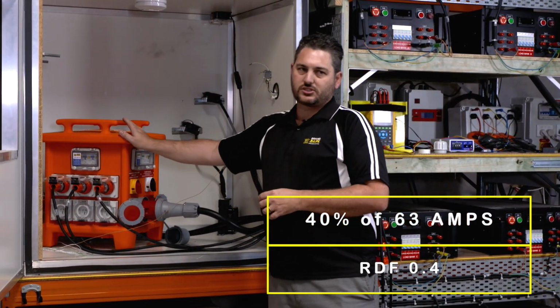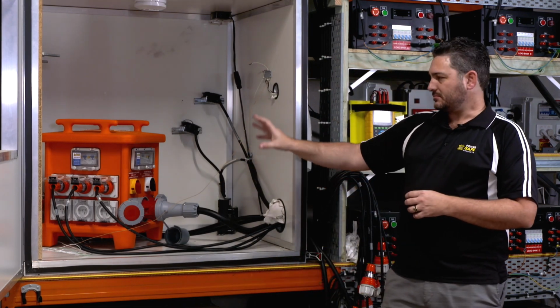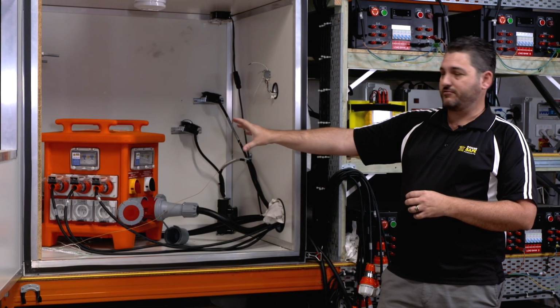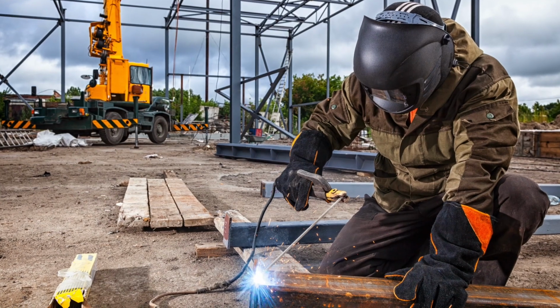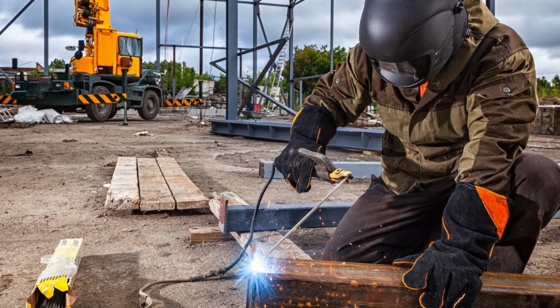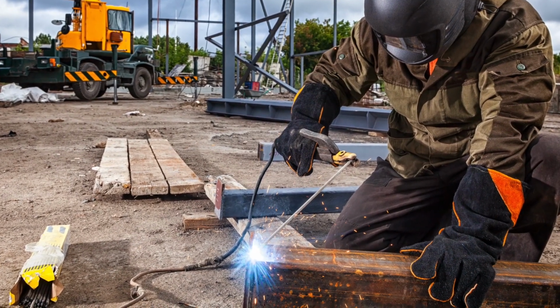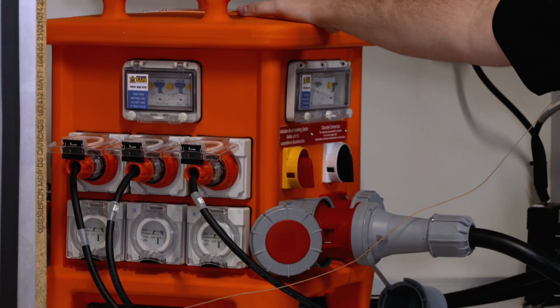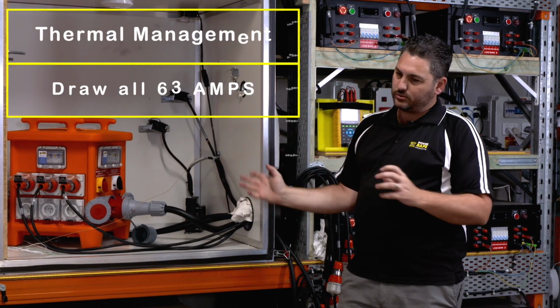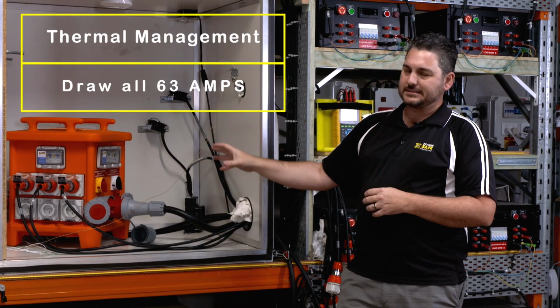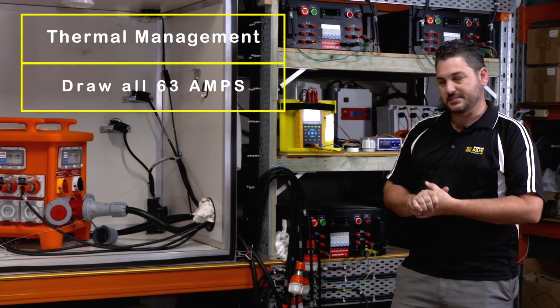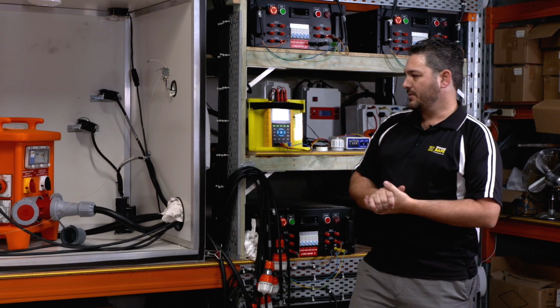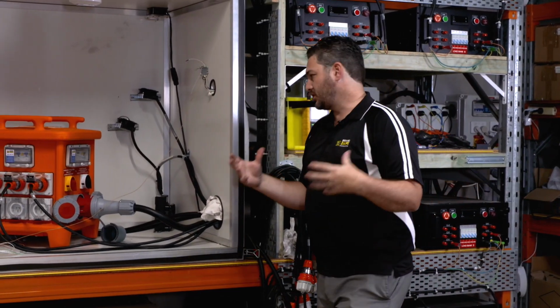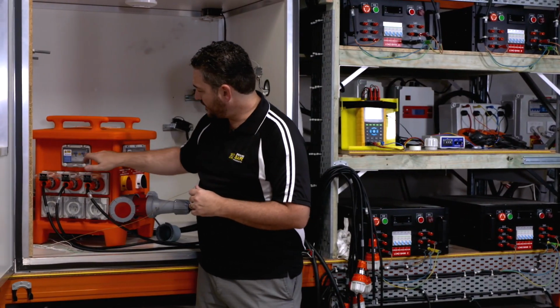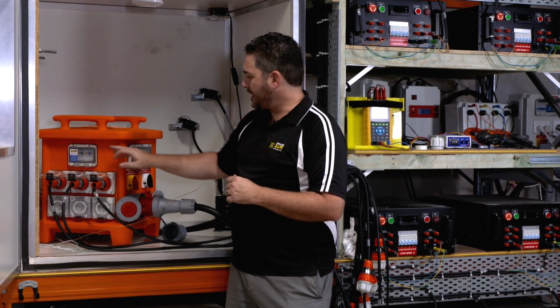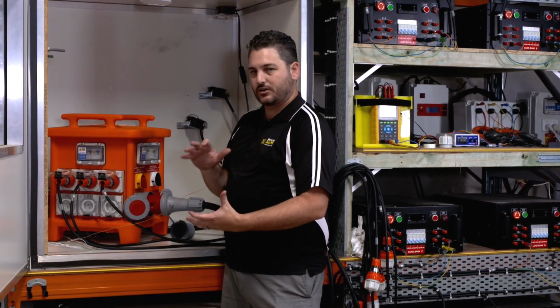So if that's going to a site with sporadic use, that board as it sits would work fine. If it's going to a mine site where they're doing welding, using heavy equipment, you will then use our thermal management system on that board, which will allow you to pull the whole 63 amps while maintaining the board below that specified temperature range. That temperature range is guided by your individual componentry. So the manufacturer of all these parts gives you a temperature range which it can operate to.